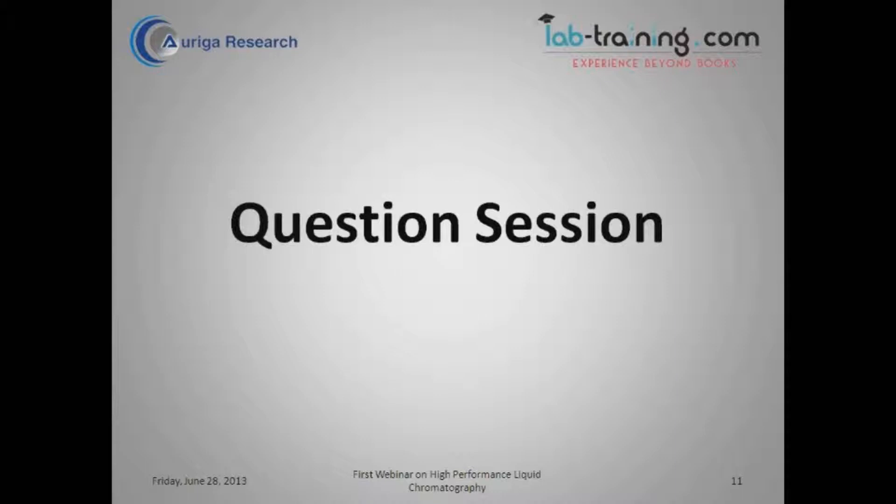Okay, I would also like to add here that if you are lucky enough to have a sample of what you are going to be analyzing routinely on the system, it makes sense to go and do a joint analysis or a demo analysis of your own sample in the lab. So theoretically a configuration might work but it is possible you will end up with a system in your lab which is not able to do the analysis. So I personally believe when I am buying any instrument, I like to go with my samples to the lab of the instrument supplier and make them analyze it using the method I am going to be using and look at the results. So only once I am satisfied with the results that I go ahead with the purchase. So I hope that answers your question.